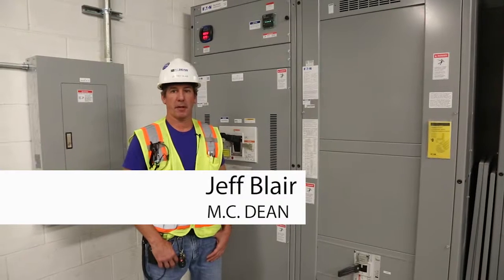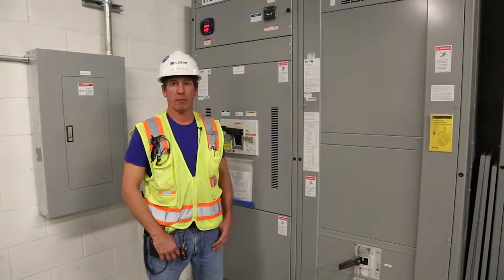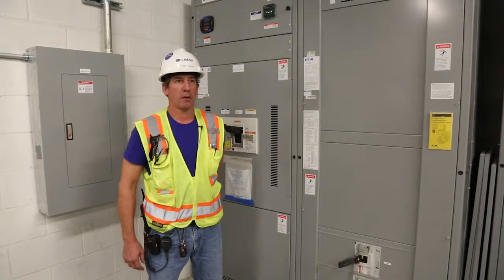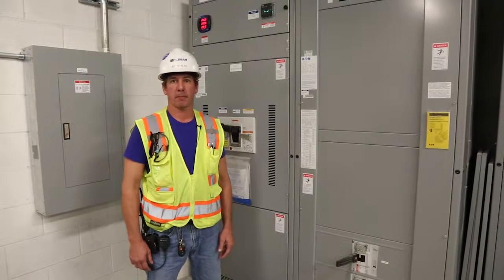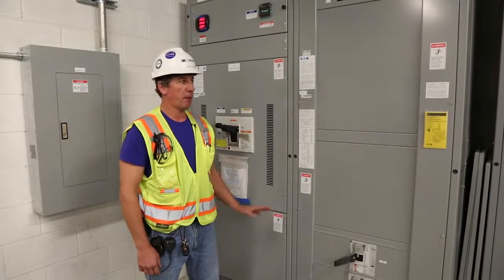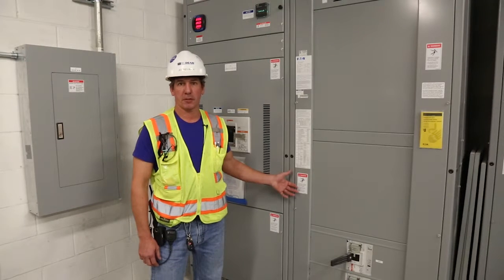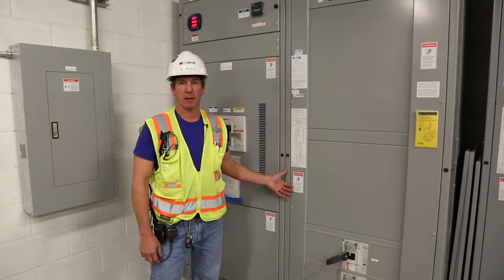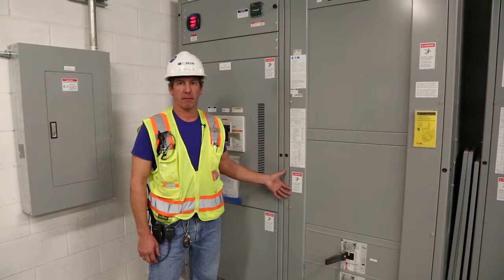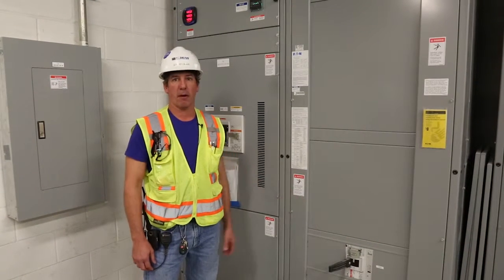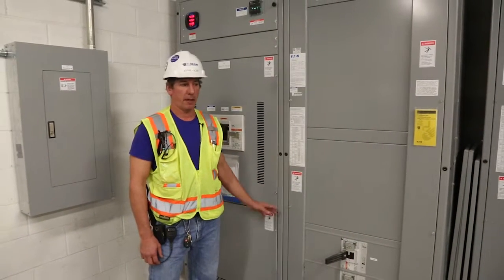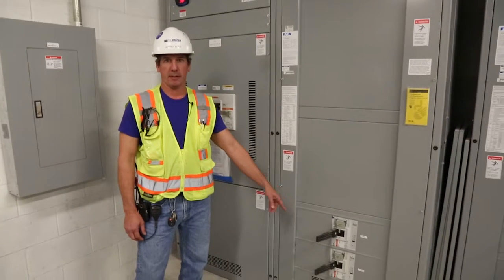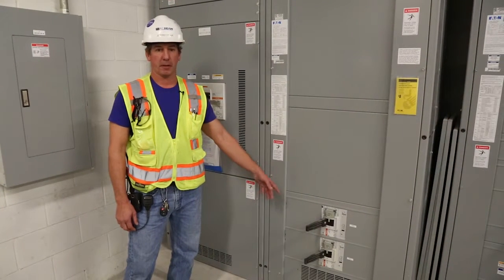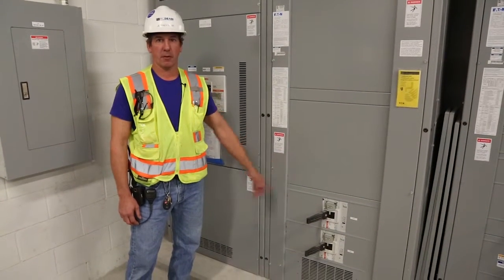All right, we're in main electrical room 140, and we're going to be going over the main distribution for this project. Right now we are at electrical switchgear HA, whose primary function is to control all the power in the north tower. It has two breakers, HDP2 and HDP1. These two breakers primarily just feed the north tower.